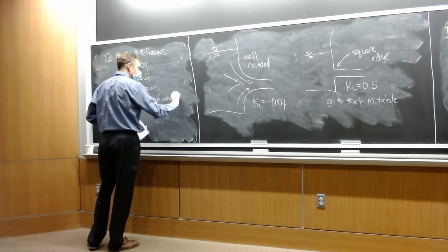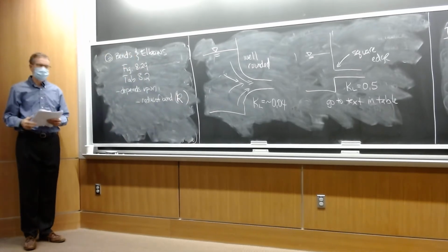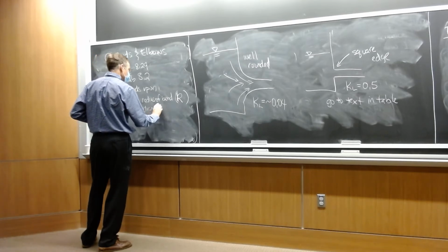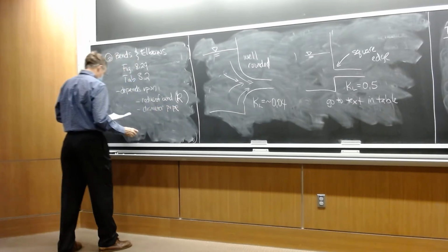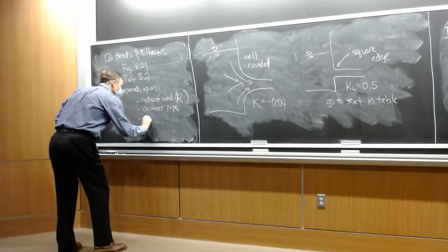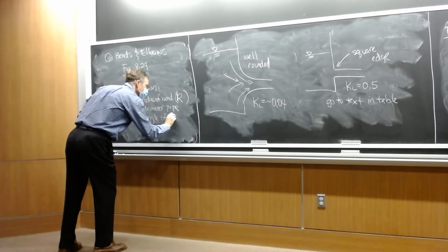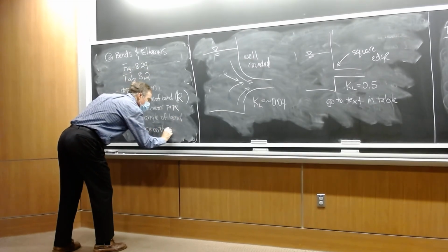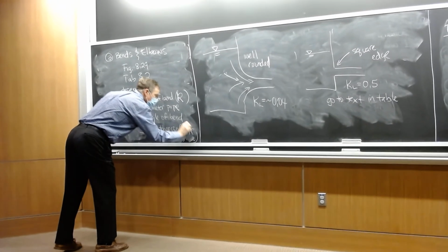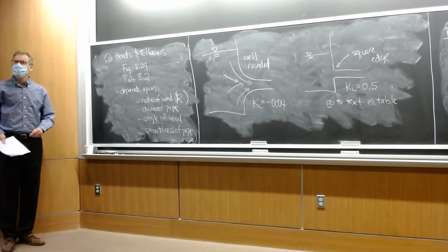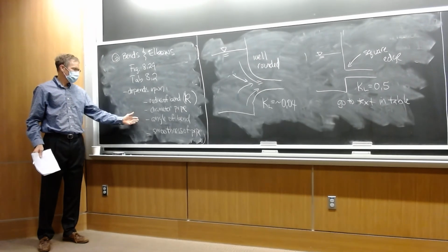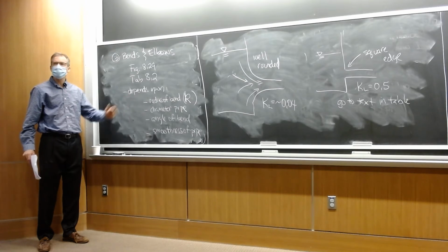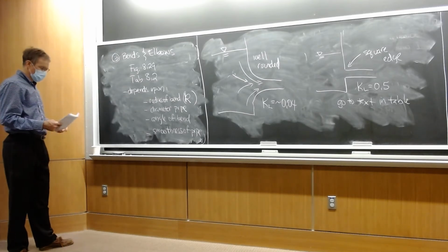They do this stylized R to give K as a function of the radius of a bend, and the 45, 90, 180 angle, smooth to rough pipe, small diameter to large diameter pipe, small radius to large radius bend.